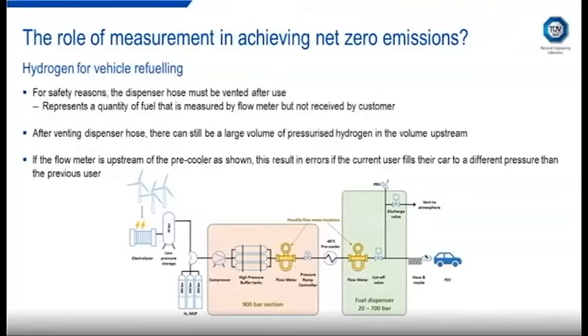Now, there are various sources of measurement uncertainty here. First of all, the temperature and pressure ranges could be challenging for the flow meter, but we also have things like the dispenser hose, which must be vented after use for safety reasons. So that represents a quantity of fuel that's been measured by the flow meter but not delivered to the customer. So that has to be accounted for, otherwise it forms part of the measurement error.